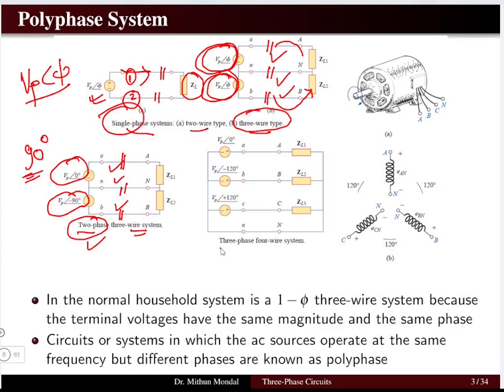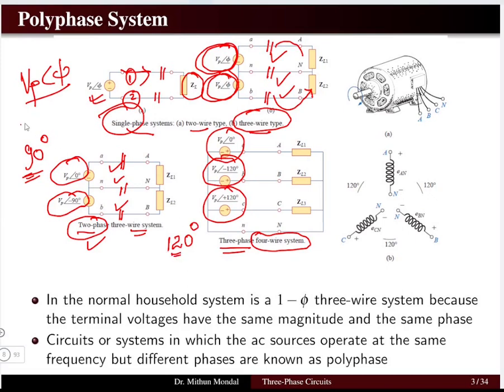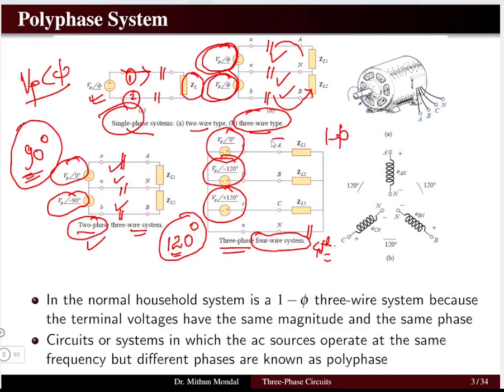In the polyphase system, we most commonly use a three-phase system with a four-wire configuration. All three voltages in a three-phase system are out of phase with respect to one another at 120 degrees — compared to 90 degrees for two-phase. There is an additional neutral wire, which is the fourth wire. This allows us to also derive a single-phase system using one line wire and the neutral wire.